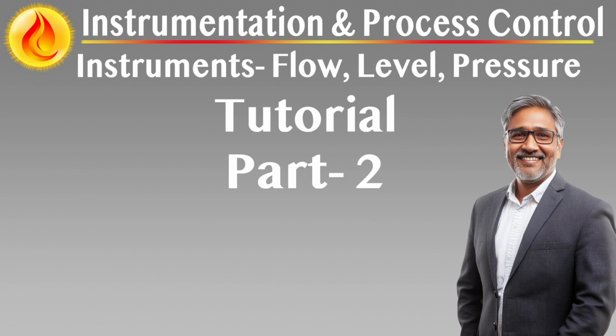For measurement integrity, placement must avoid nozzle impingement zones or vortex areas, locations near pump suctions, control valves, or elbows that may distort flow or pressure, high points in liquid lines, gas pockets, or low points in gas lines, liquid traps that introduce measurement error. Field readability and physical access are equally essential. Local indicators must be visible from operator working positions, especially for equipment requiring manual intervention, backlit or shaded if subject to glare or poor lighting conditions, readable from walkways or platforms without stretching, leaning, or unsafe postures.